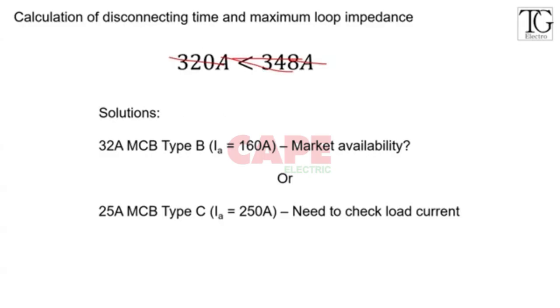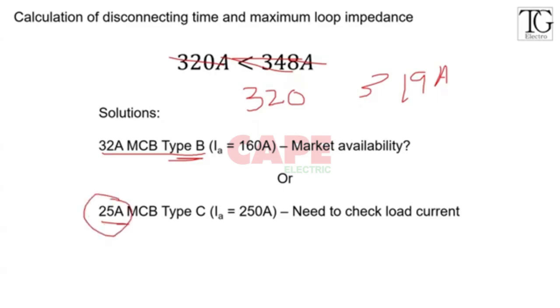If the fault current is going to be less than 320 amps, even if it is 319 amps, then you are supposed to change the MCB from type C to type B, or you are supposed to decrease the size of the MCB to 25 amps. So you can do both of these changes. You can either change the tripping curve from type C to type B, or you can change the rating of the MCB from 32 amps to 25 amps. So these two things can be done.